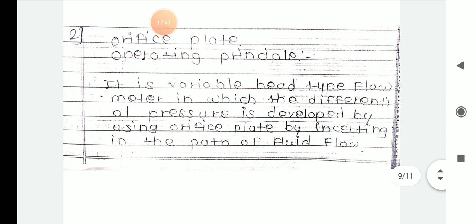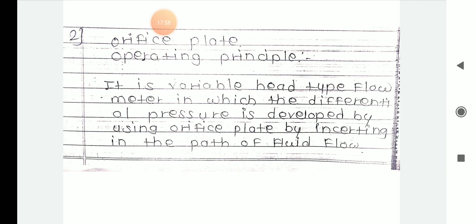Next we will move on to the orifice plate operating principle. It is a variable head type flow meter in which differential pressure is developed by using an orifice plate. Here you directly apply the orifice plate by inserting it in the path of fluid flow. This is the diagrammatic representation of the orifice plate. These are the plates: concentric, eccentric, and segmental.